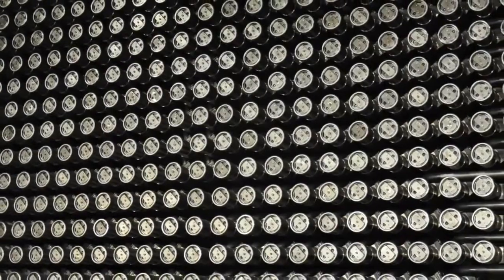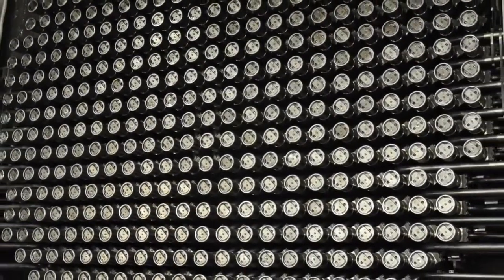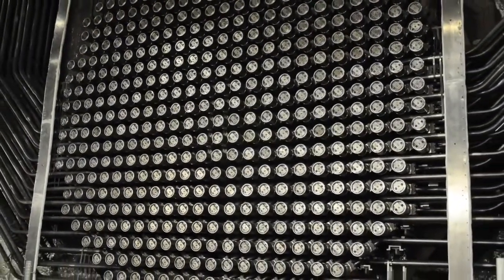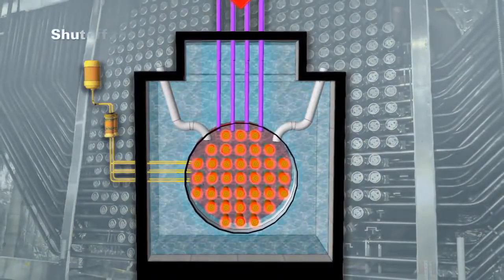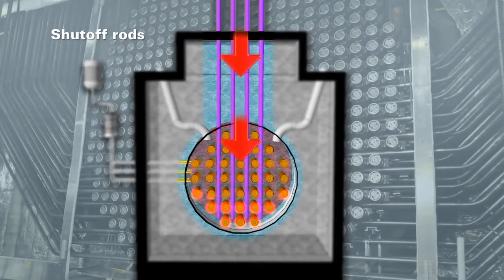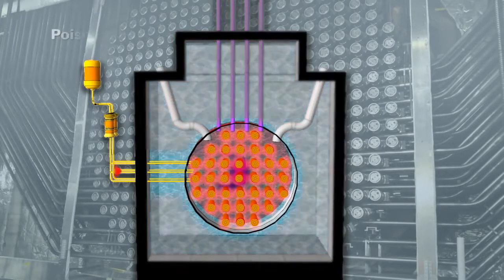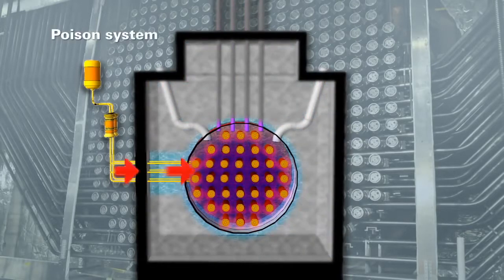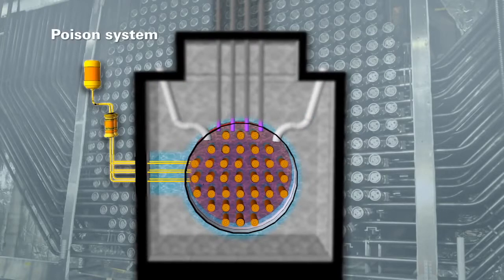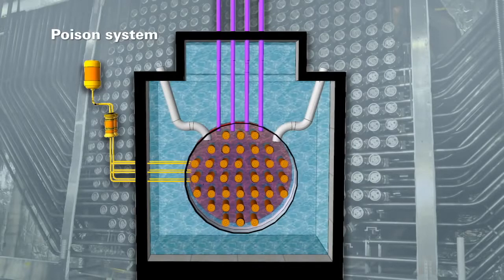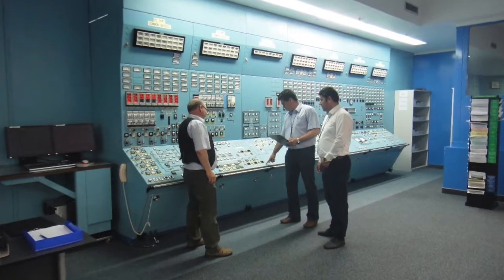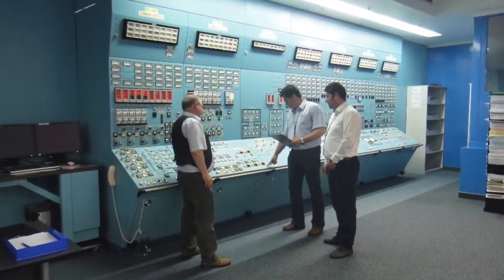Nuclear reactors have two independent, fast-acting and equally effective shutdown systems. The first shutdown system is made up of rods that drop automatically and stop the nuclear reaction if something irregular is detected. The second system injects a liquid, or poison, inside the reactor to immediately stop the nuclear reaction. Both systems work without power or operator intervention. However, they can also be manually activated.